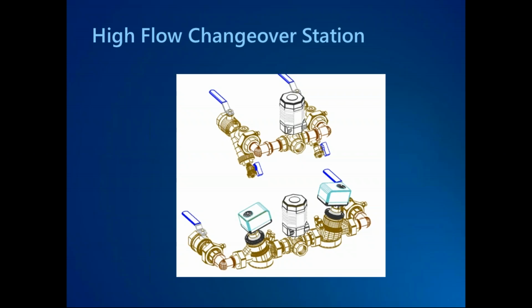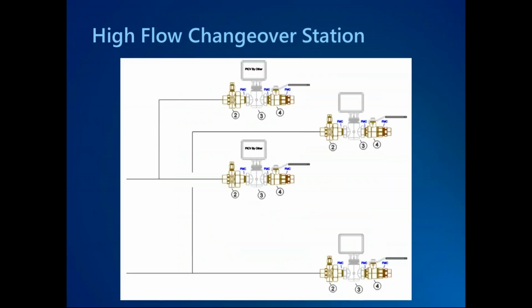So what I recommend, and what I think we're seeing more and more in the market, is use the 6-ways where applicable, but don't be afraid to step back from that and go back to the quote unquote fixed solution we looked at in the very beginning, using 4 separate control valves. If it doesn't make sense to try to fit the round peg of a 6-way design into the square hole of a large flow application, let's go with a tried and true solution, which is just 2 on-off control valves, 2 control valves that either do modulating or are a PICV, and then they're just specifying is hot or cold water going to the zone at the time.